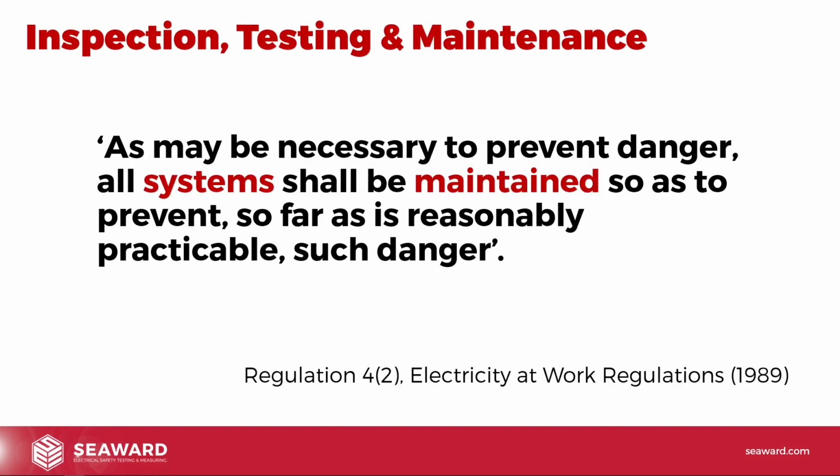So just to recap, because I think this feeds into what we're going to look at with risk assessment. The main piece of legislation relating to PAT testing, or that justifies PAT testing, is under the Electricity at Work Regulations 1989. It's Regulation 4, Paragraph 2. And this is a copy of a quote from it, and it says, as may be necessary to prevent danger, all systems shall be maintained so as to prevent, so far as is reasonably practicable, such danger. So what this is saying is we've got a legal duty to maintain systems to prevent danger.